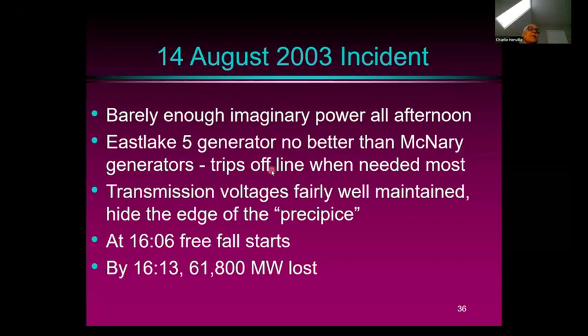So on the 14th of August in the year 2003, there was another incident, this time on the east side of North America. And in this case, there was barely enough power, imaginary power, all afternoon. And then there was a major generator at East Lake Power Station, which tripped offline when it was needed most. But the transmission voltages were fairly well maintained, and this hid the edge of the precipice. So this is what I'm saying, that the precipice is often very hard to anticipate.